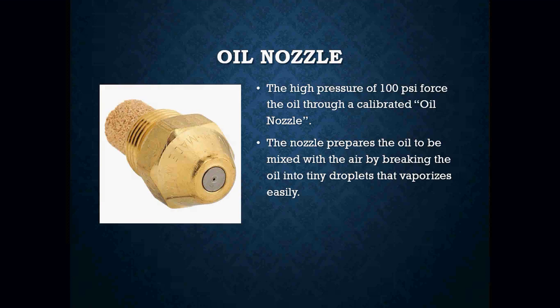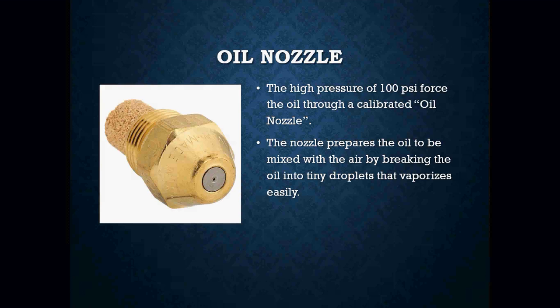You will have your oil nozzles. The high pressure of 100 psi forces the oil through a calibrated oil nozzle. The nozzle prepares the oil to be mixed with air by breaking the oil into tiny droplets that vaporize easily. Oil needs to be atomized in order for it to burn. By shooting oil through a small calibrated hole, we make the oil vaporize, so when I add a spark from my electrodes, I am able to burn the oil. It also meters the oil in the correct amount, and as the oil leaves the nozzle, it is set into a swirling pattern to help it mix with the air.